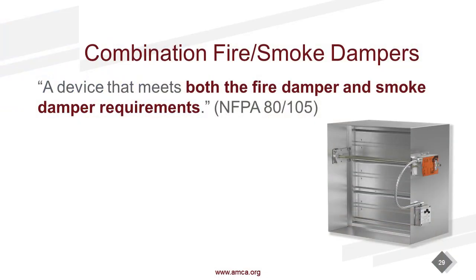So now we've isolated and trapped that smoke, and we have our return dampers open on the 2nd floor. We're able to evacuate that. That would be a non-dedicated HVAC smoke control system. Pretty typical. So again, that would be your Chapter 9 NFPA 92 use of your smoke dampers. Combination fire smoke dampers. It's pretty simple. Everything I just talked about, from fire dampers to smoke dampers, in one device. In the past, if you had a penetration requirement that needed fire protection and smoke protection, you needed 2 dampers.